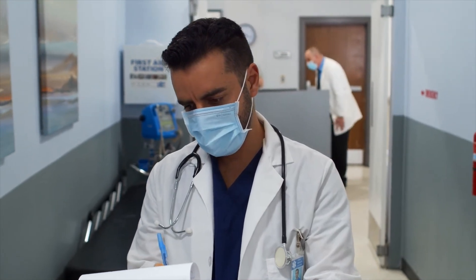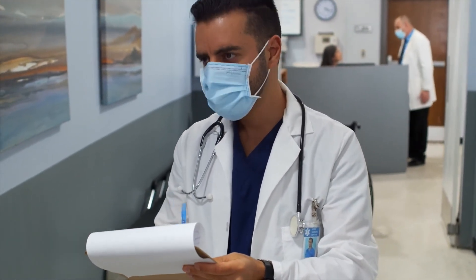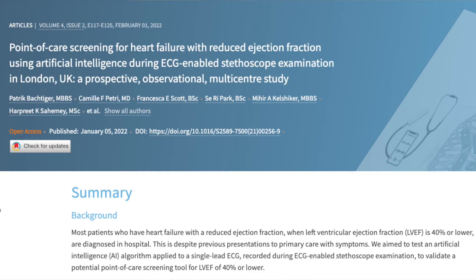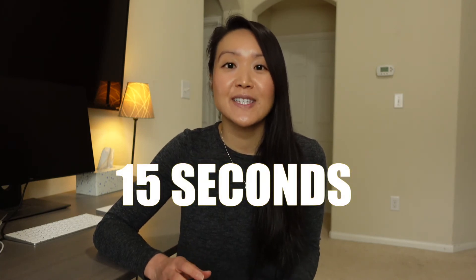It wasn't until recently that research was done and published on how effective this tool can be in the clinical setting. The UK NHS ran an independent study evaluating the use of the Eko DUO with the low ejection fraction algorithm to identify patients with heart failure. The study was tested on more than 1,000 patients and showed an accuracy of 81%, correctly identifying patients with left ventricular ejection fraction less than 40%. If the user did a recording on two chest locations, the accuracy of the AI jumped to 86%. This study showed that the AI tool can screen for heart failure in 15 seconds during a standard physical examination.